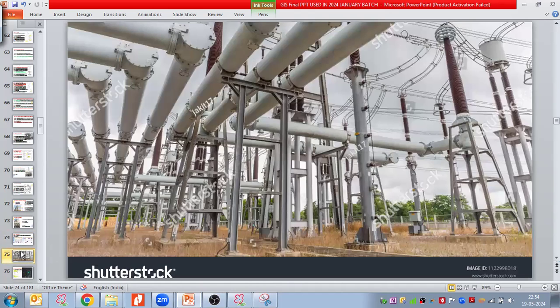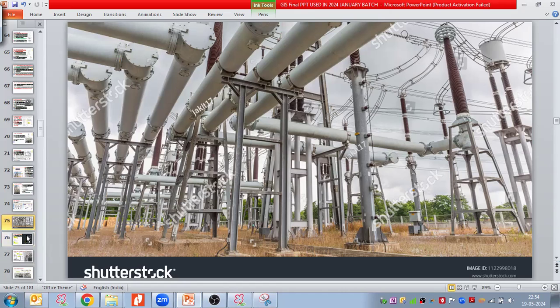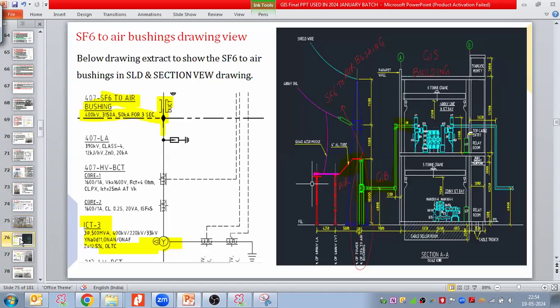So let us see some photos of the duct and the SF6 to air bushing. Here we have the wave trap, and this equipment is representing the gas to air bushings, and this is representing the gas bus duct. In that bus duct, the SF6 gas is flowing. Right. So how does this equipment, this SF6 to air bushing, appear in the drawing?